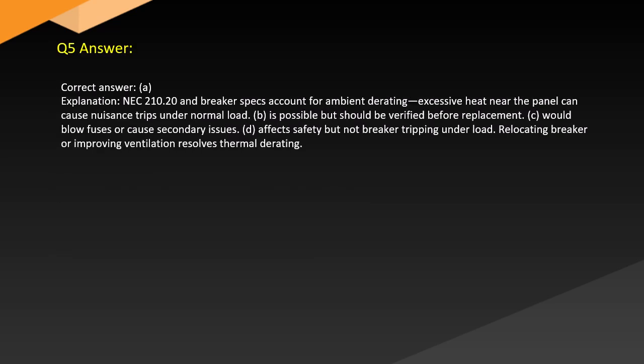Answer. Correct answer: A. Explanation. NEC 210.20 and breaker specs account for ambient derating. Excessive heat near the panel can cause nuisance trips under normal load. B is possible but should be verified before replacement. C would blow fuses or cause secondary issues. D affects safety but not breaker tripping under load. Relocating the breaker or improving ventilation resolves thermal derating.